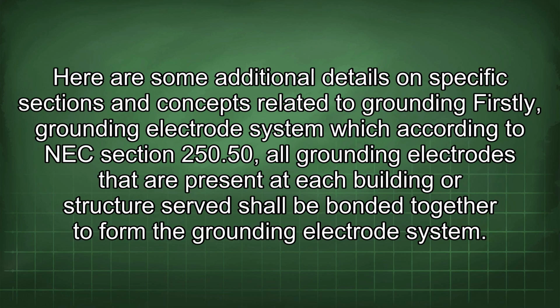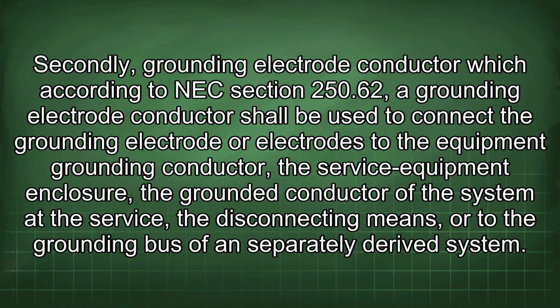equipment. Here are some additional details on specific sections and concepts related to grounding. Firstly, grounding electrode system, which according to NEC section 250.50, all grounding electrodes that are present at each building or structure served shall be bonded together to form the grounding electrode system. Secondly, grounding electrode conductor, which according to NEC section 250.62, a grounding electrode conductor shall be used to connect the grounding electrode or electrodes to the equipment grounding conductor, the service equipment enclosure, the grounded conductor of the system at the service, the disconnecting means, or to the grounding bus of a separately derived system.